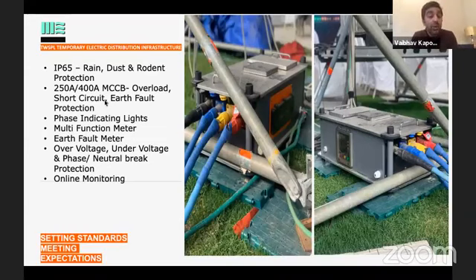If there is a neutral break, in a normal case, if the neutral breaks, there is 440 volts of electricity and everything will burn on site. In a worst case scenario, the neutral breaks on site. If by chance it does, my systems inside will again trip the MCB.